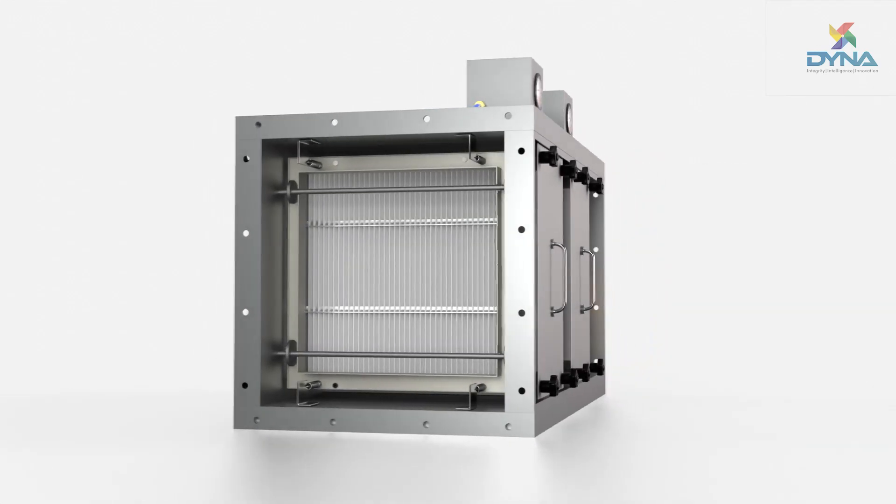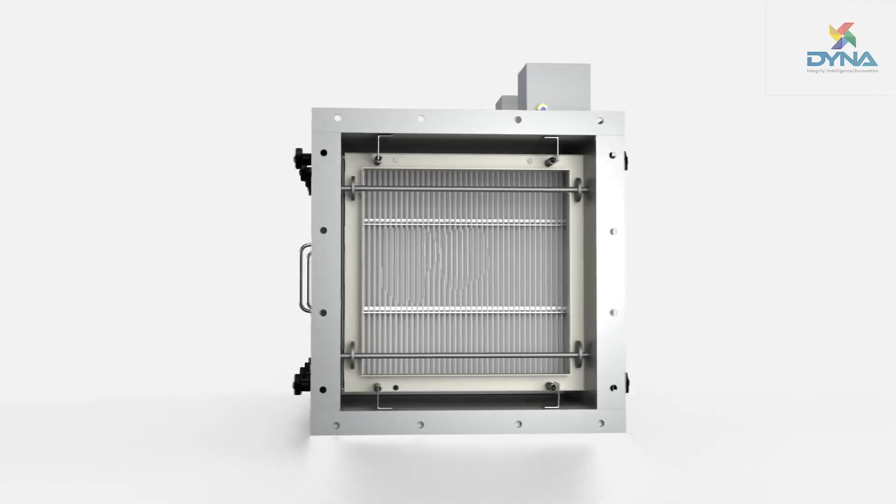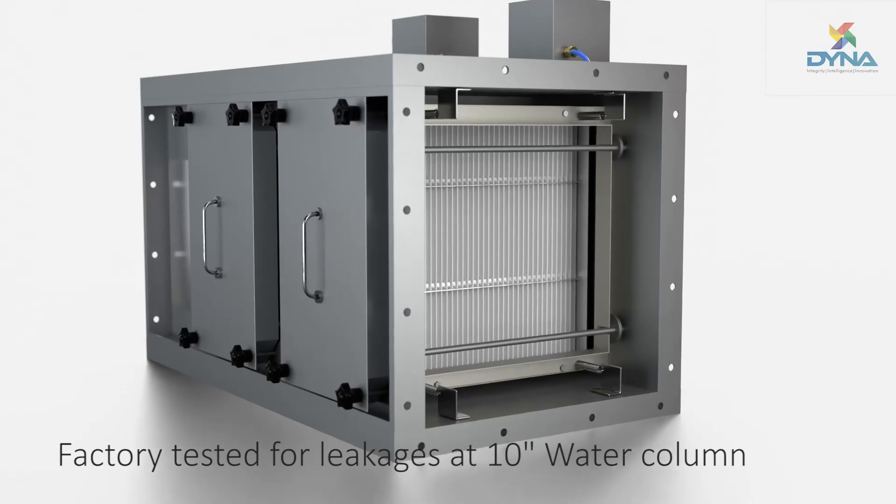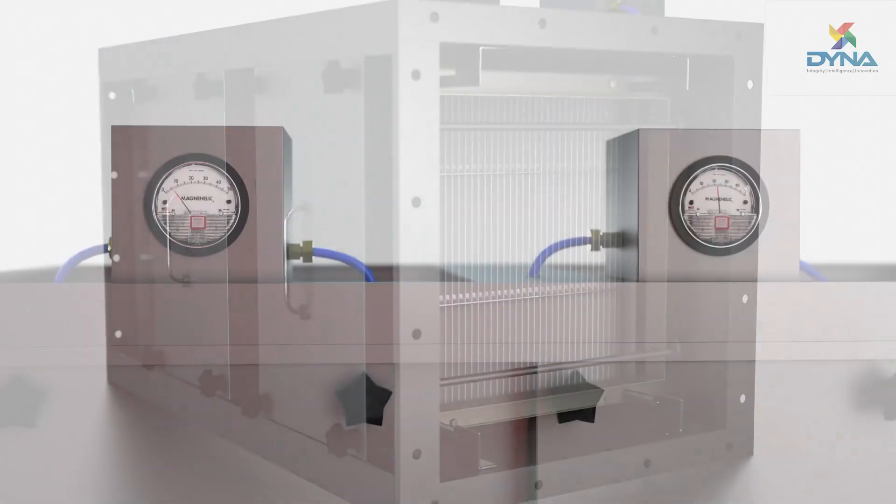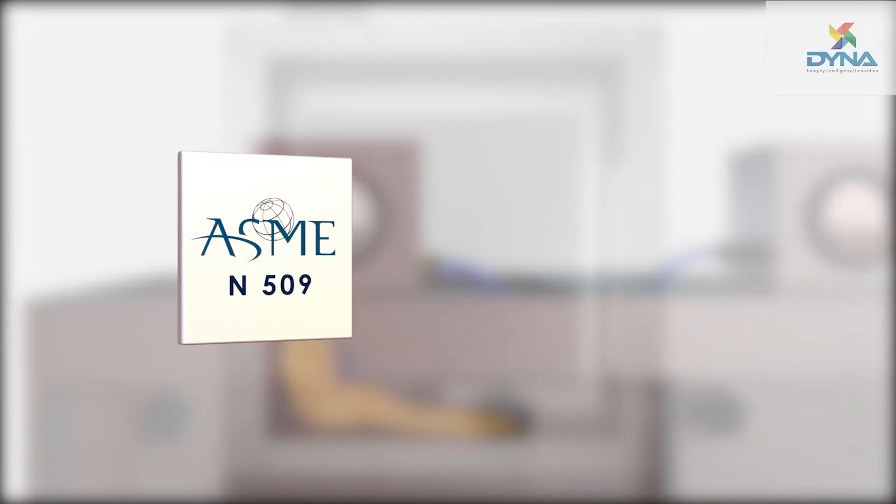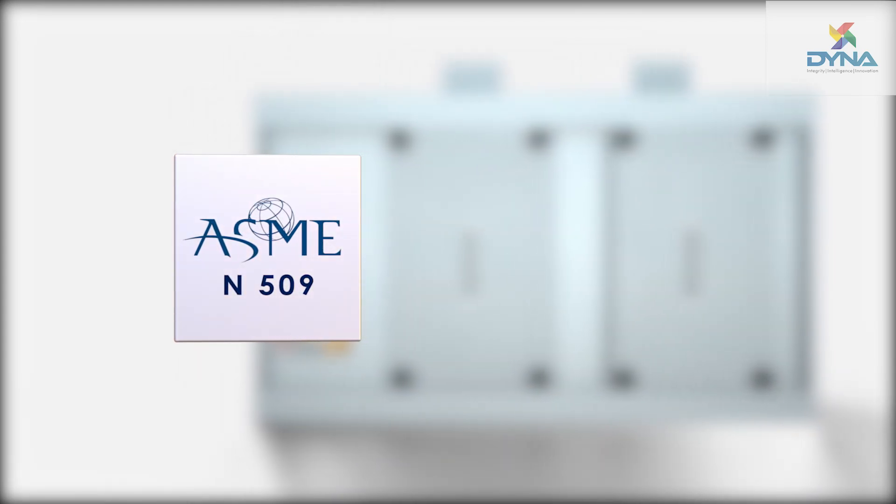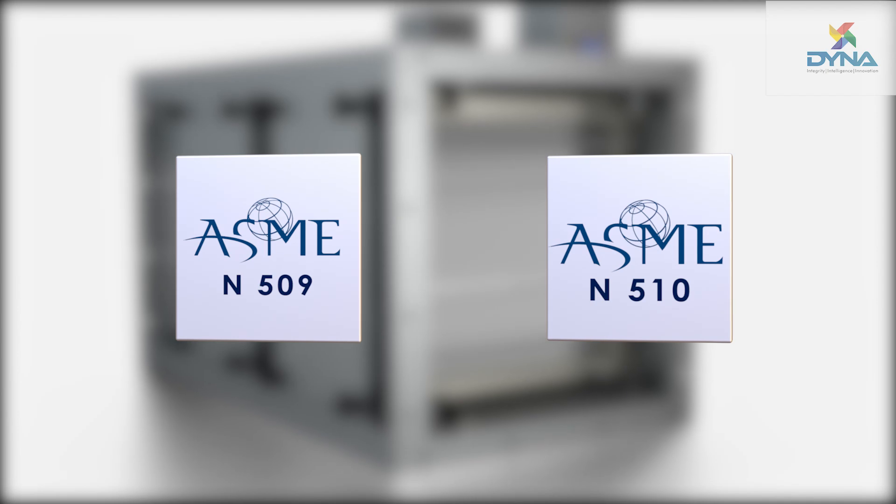Also, each filter unit is designed to withstand plus or minus 20-inch water gauge and factory tested to plus 10-inch water gauge in accordance with ANSI ASME N509 and N510 to ensure overall housing integrity.